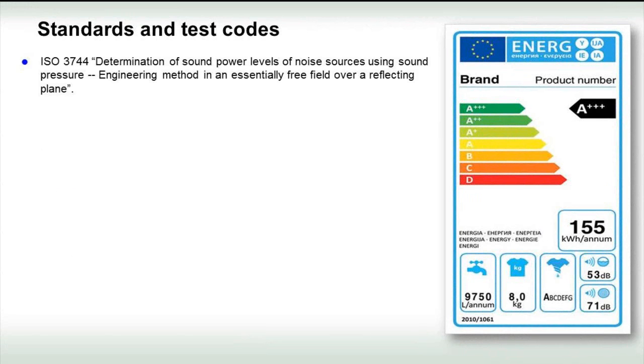The measurements are based on ISO 3744, determination of sound power levels of noise sources using sound pressure, engineering method in an essentially free field over a reflecting plane.